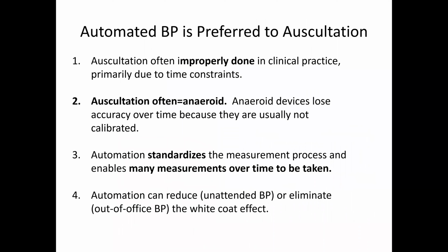Why is automated preferred? I've already touched on most of this because auscultation is often improperly done, because auscultation often means aneroid, and if aneroids are not calibrated, they're off, guaranteed. Also because automation standardizes the measurement process, so it takes away the need to do all of the maneuvers required with auscultation. And there are, of course, still many things left to do with measurement, like proper positioning, proper cuff size, etc. But at least it standardizes part of the measurement process.